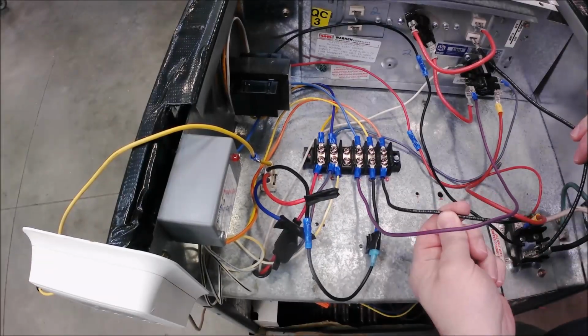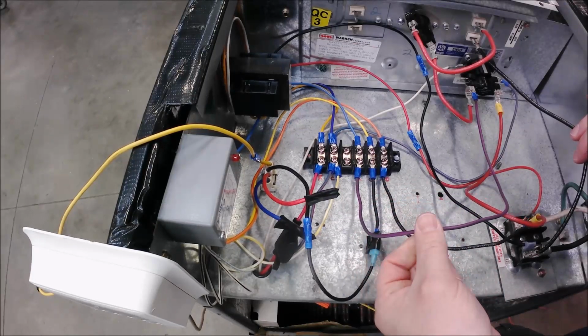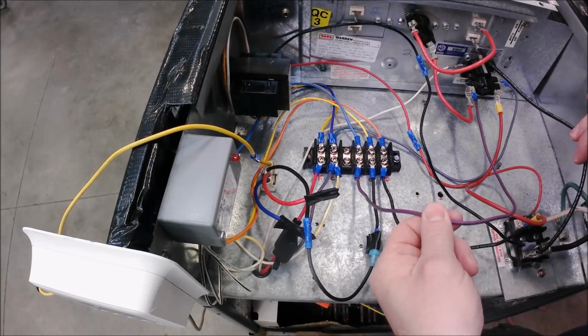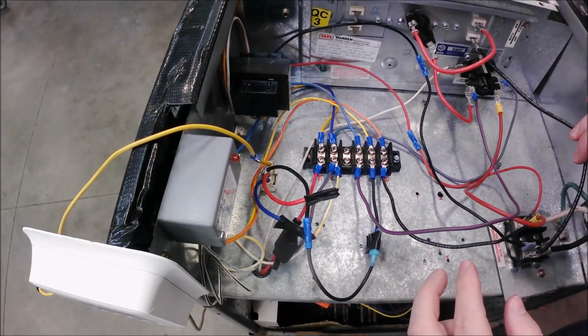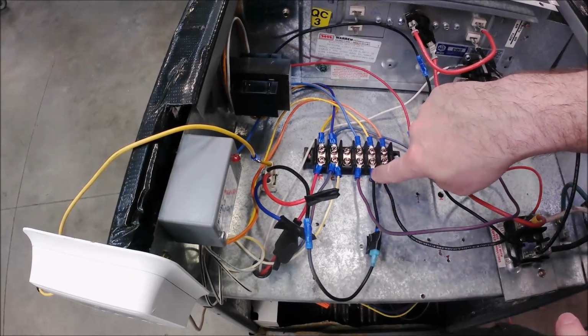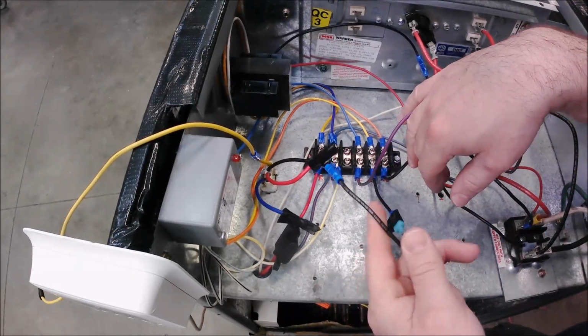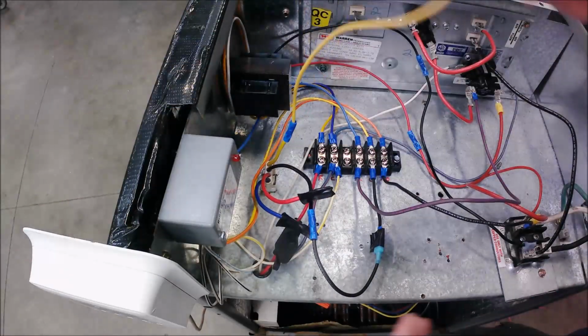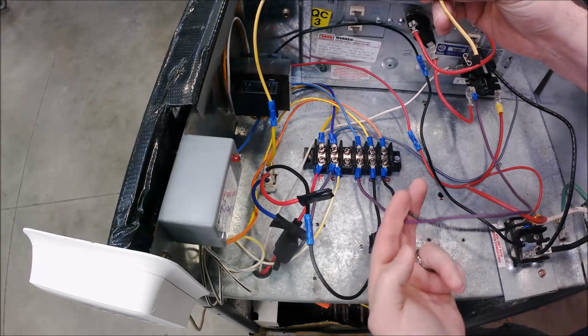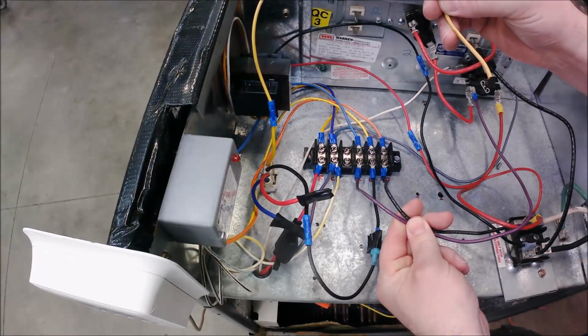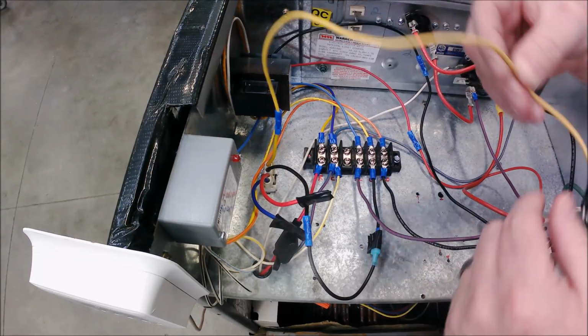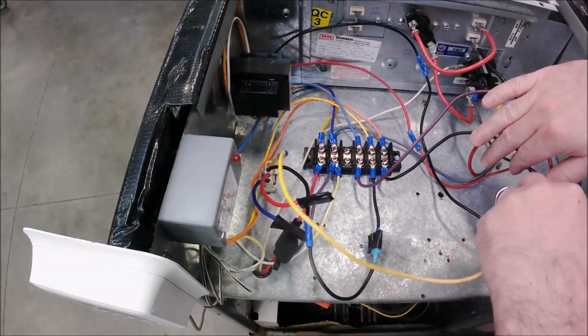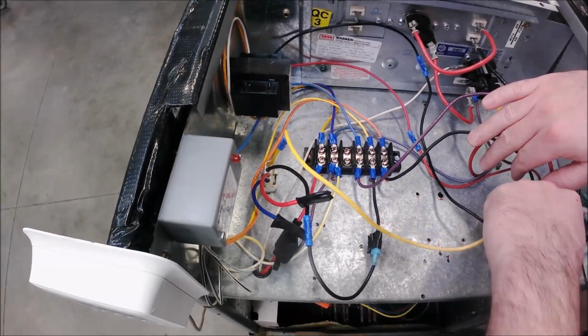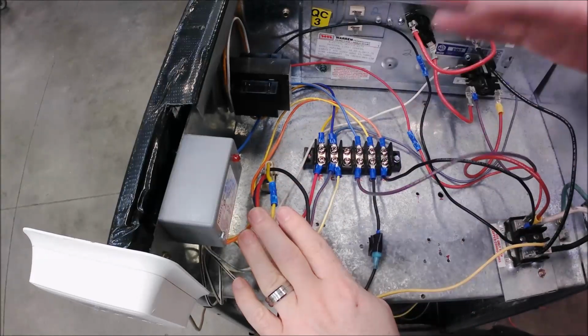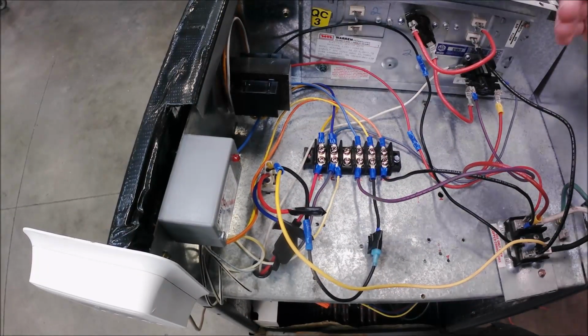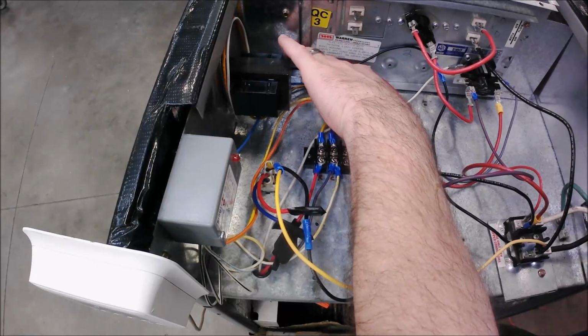Now, since we have our L1 going into the normally open, and we have basically L1 coming from the heat strip circuit off the sequencer, both of those are L1 going either circuit into the relay, and they're coming back on the common going to our fan speed. The one thing we have left to do is to terminate the other side of our PSC motor, and since either one of these, purple or the normally closed or the normally open, they're both L1, so this wire right here has to be L2, and we're going to terminate L2 over here on this bottom side of this terminal block. And with that being said, everything else is already wired, so a circuit at a time, you can chip away and wire it back up.